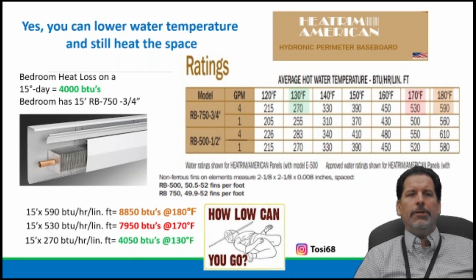Think about a boiler. You know you sized it right on a design day when it doesn't turn off. It's actually the perfect size for the house load, not individual rooms, unless you're zoning or micro zoning everything. But this is what we're talking about: lowering water temperature while still delivering the comfort, the BTU delivery, because we did the math.